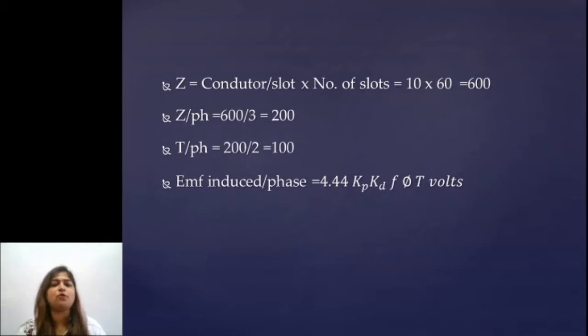Now we substitute all values in EMF equation. EMF equation is given by 4.44 Kp Kd F Φ T. You are given with winding factor Kw which is nothing but equals to Kp Kd. So we will directly substitute Kw and out of this equation Φ is unknown. Substitute everything and get the value of Φ which comes out to be 49.46 mWb. So now this is the first part of the problem.